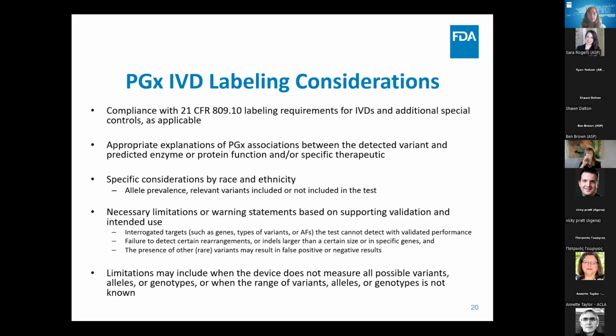And so in considering what limitations might be needed, one generally can consider the validation provided and any bias in accuracy estimates. So for example, positive selection bias, you would consider the sample size and margin of error for certain genotypes, for example, wide confidence intervals from low sample number. And then you'd also consider sample types used. So, was validation established using contrived or non-intended use samples?